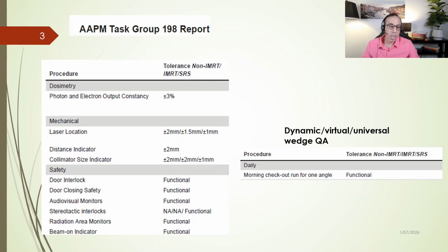And the last part is the radiation safety. These tests are different because they don't use millimeter measurement. Instead, they are strict pass or fail tests. First, we check the door interlock. Then we check audiovisual monitors. And then we make sure that beam on indicator lights are working. And if we have a radiation area monitor, we check whether it is working or not.